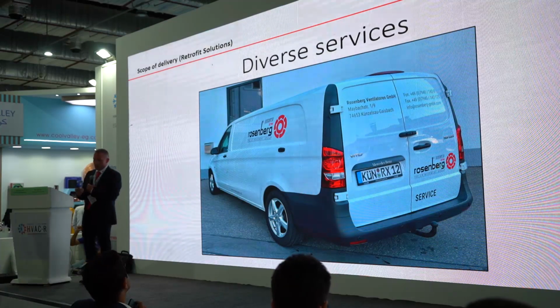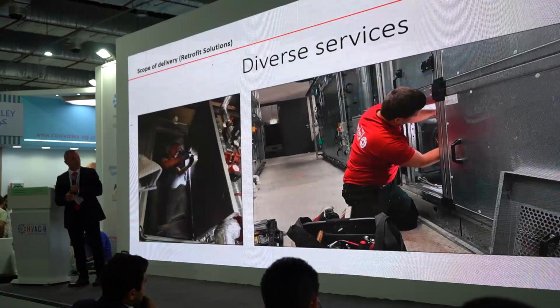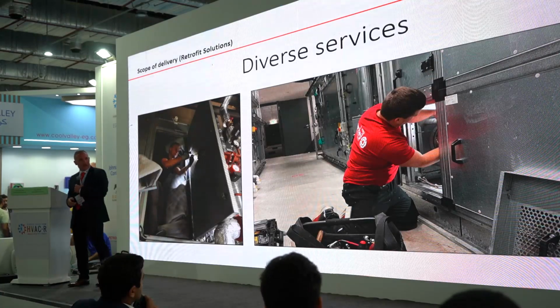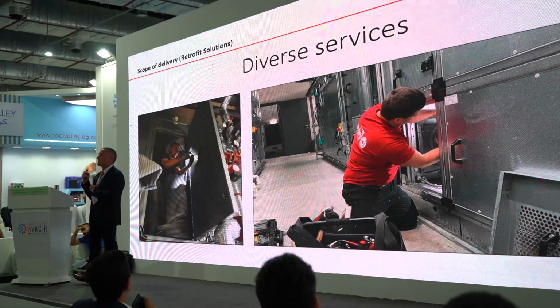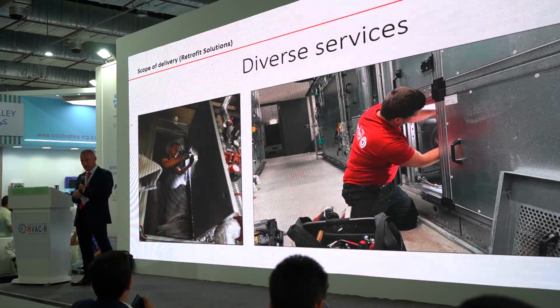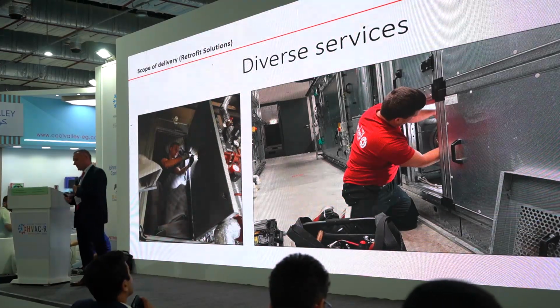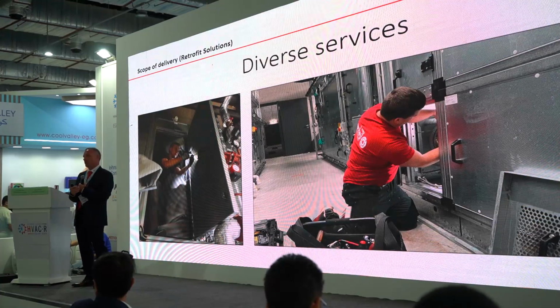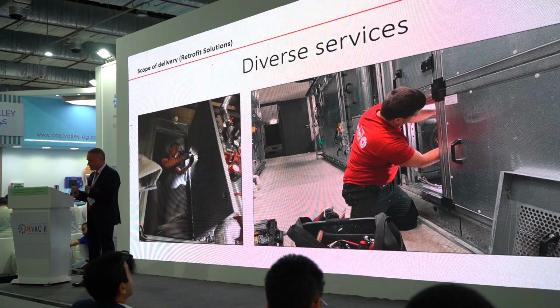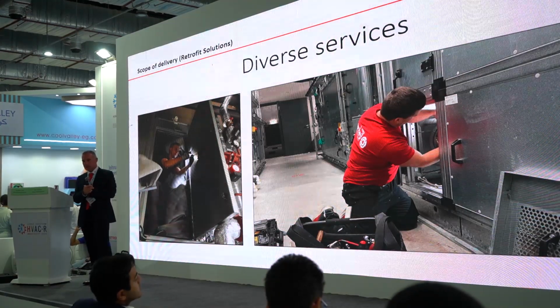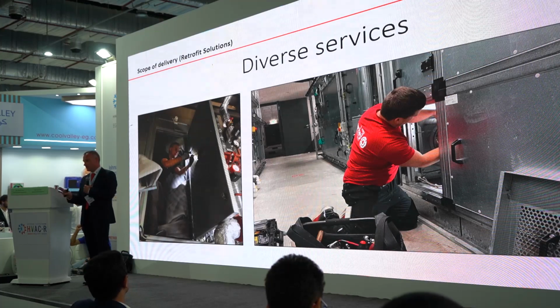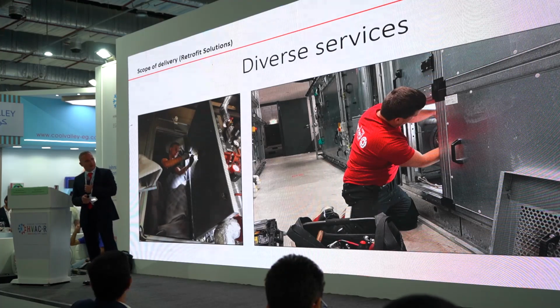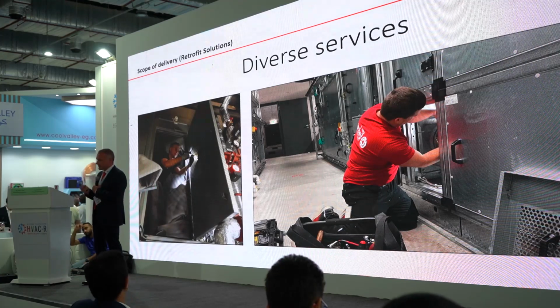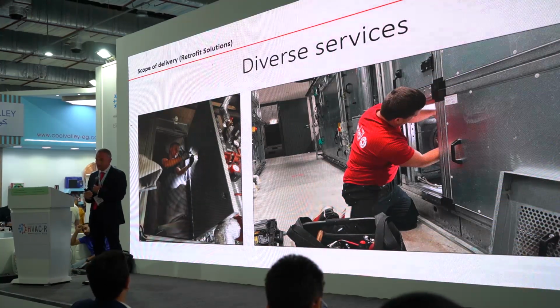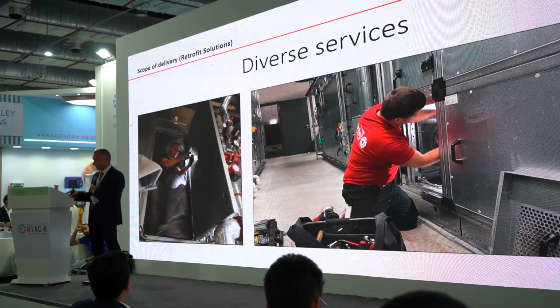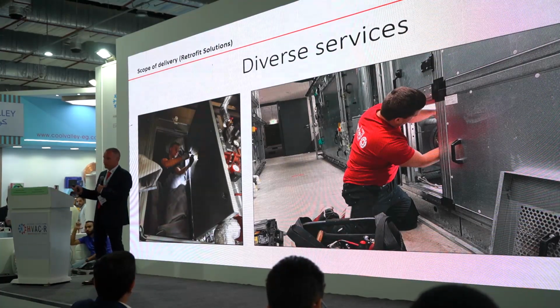In Germany we have our own service team, a nice colleague, who does the installation and measurement of the old existing air handling unit, because it happens very often that the customer doesn't even know the airflow, pressure, or dimensions. So our service goes to the customer, measures the current status of the AHU, and these values, the inner dimensions, airflow and pressure, are very important to design the right DC fan grid.